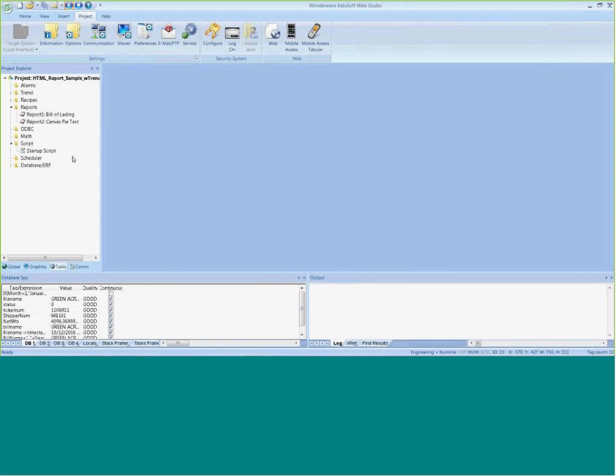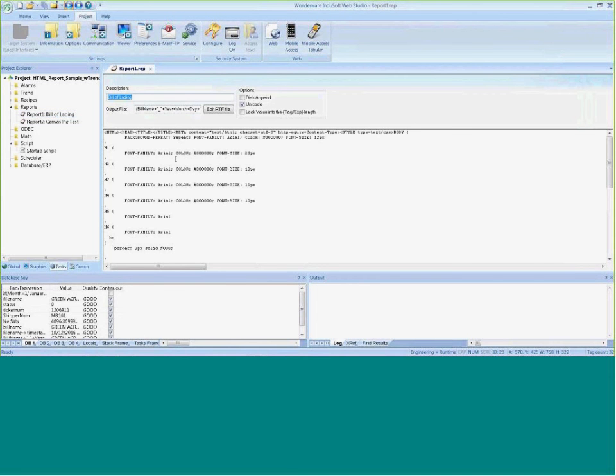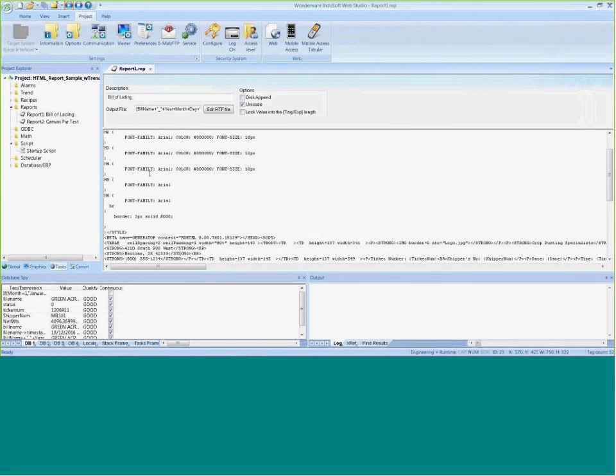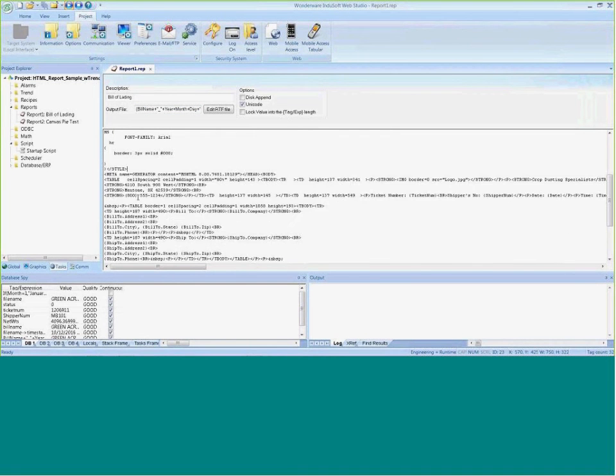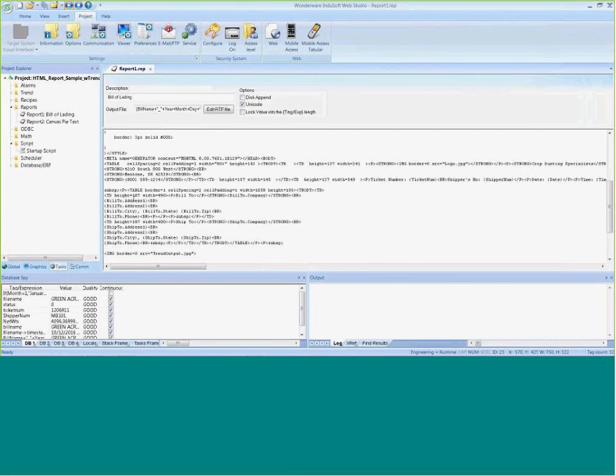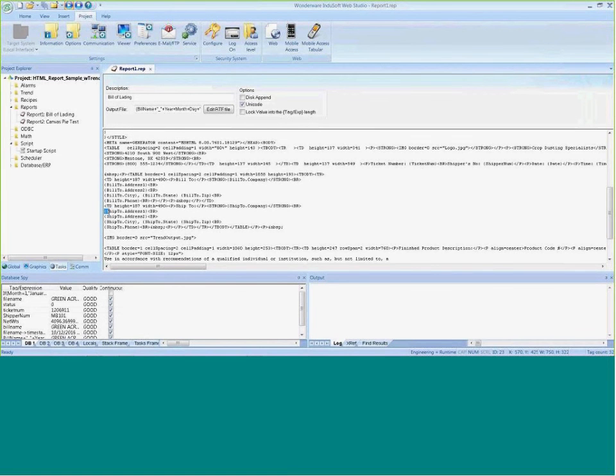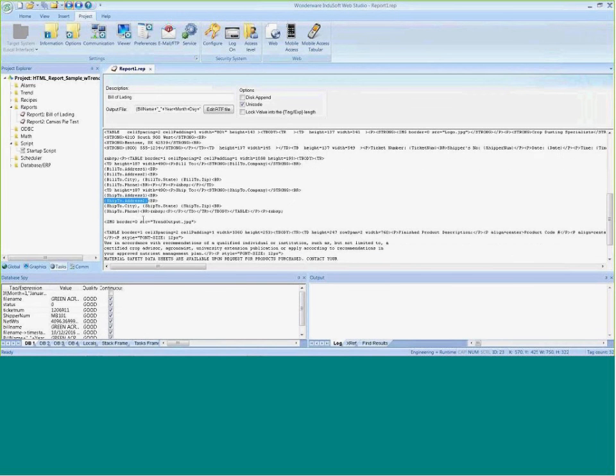Let me go back to the development environment. Our reports are normally text, but what I've done here is put HTML in the report format. When I save this, I save it with the time and date stamp and then the extension of HTML. Anywhere I need a tag, I put the tag inside of curly brackets, which shows that value. And then here I've embedded that trend output.jpg.